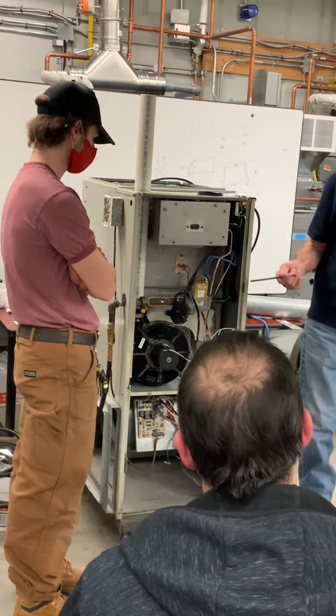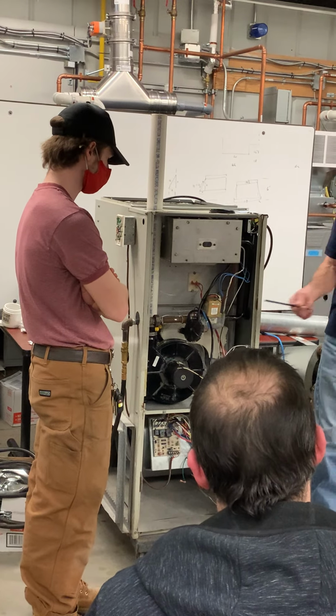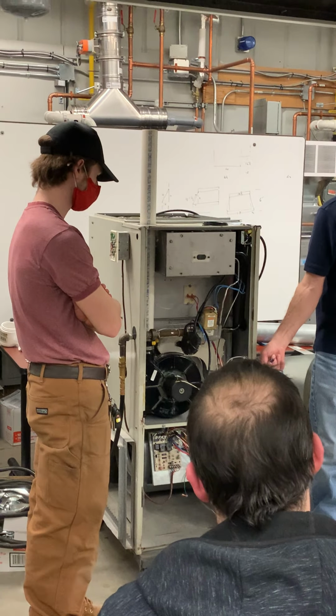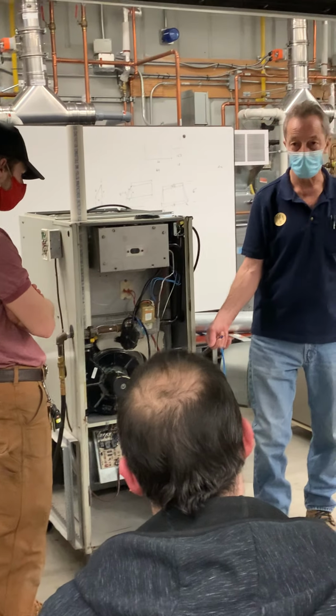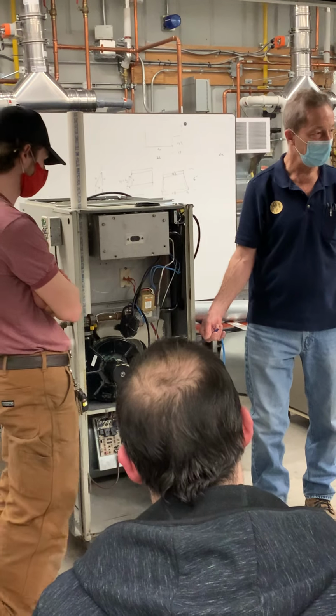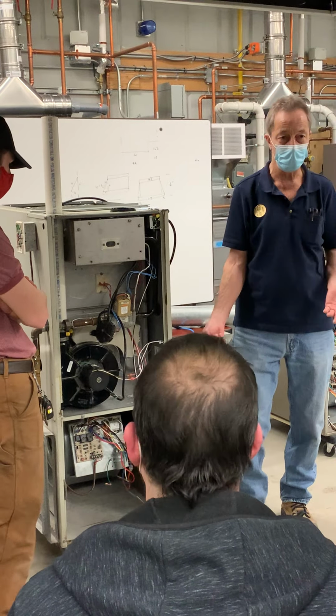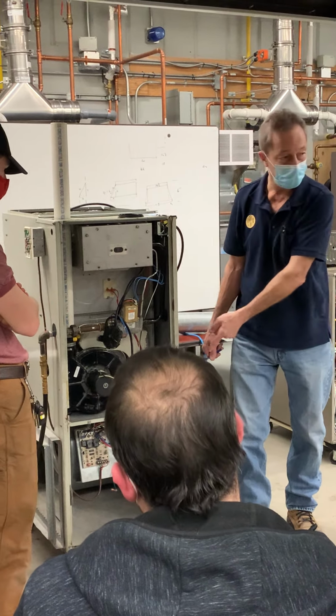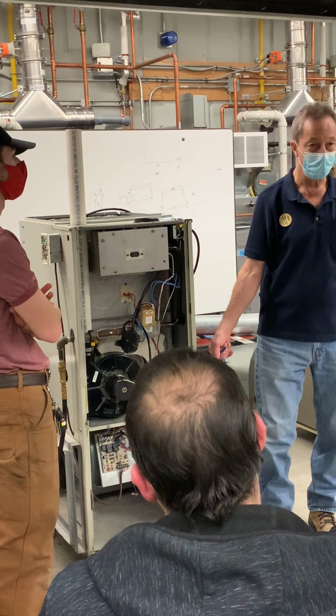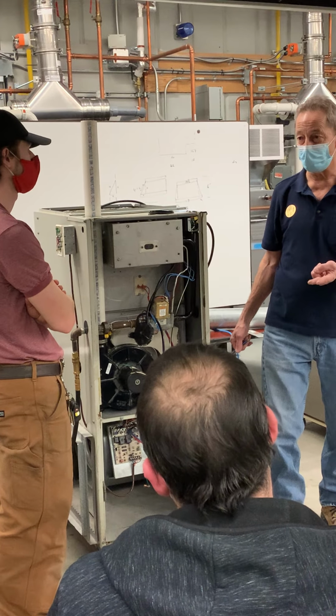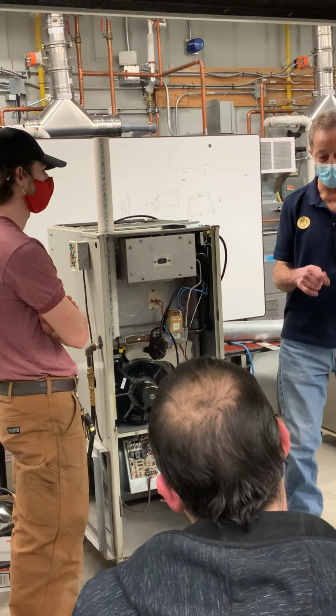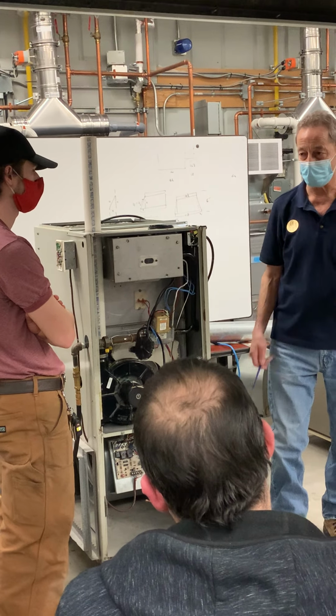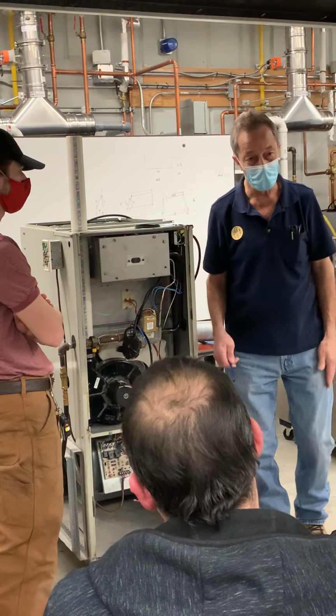As soon as you see a Honeywell Smart Valve, you're thinking, oh yeah, that orange wire energizes the board to start the timing for 30 or 60 seconds. After 30 to 60 seconds, the motor should start. If it doesn't start, hey, it could be the signal never made it to the board. Could be defective relay in the board. Could be defective board. Could be loose wire. Could be defective capacitor. Could be a seized motor. Could be open windings on the motor.